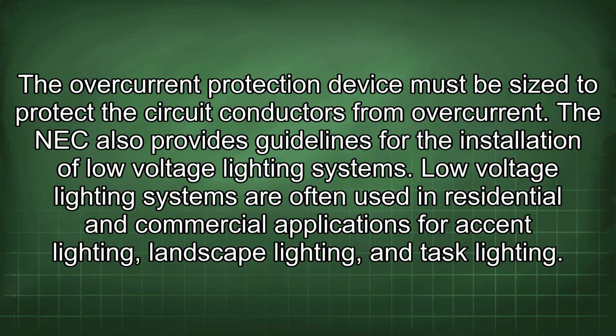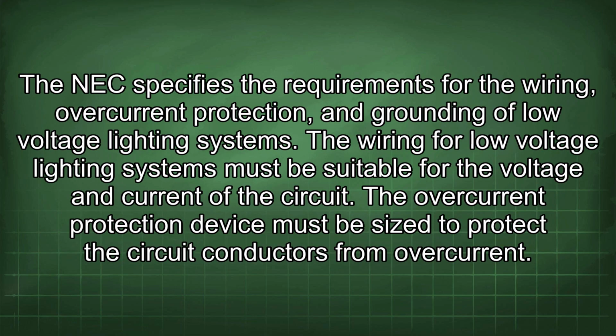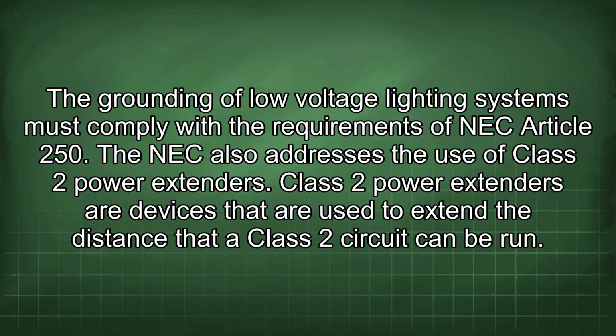The NEC also provides guidelines for the installation of low-voltage lighting systems. Low-voltage lighting systems are often used in residential and commercial applications for accent lighting, landscape lighting, and task lighting. The NEC specifies the requirements for the wiring, overcurrent protection, and grounding of low-voltage lighting systems. The wiring must be suitable for the voltage and current of the circuit. The overcurrent protection device must be sized to protect the circuit conductors from overcurrent. The grounding of low-voltage lighting systems must comply with the requirements of NEC Article 250.